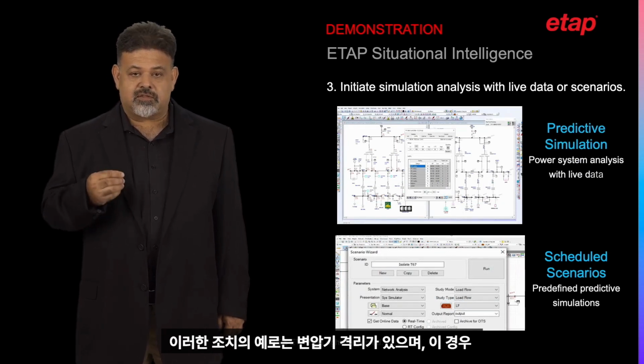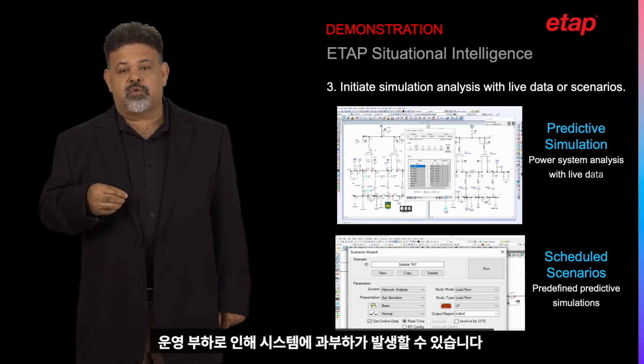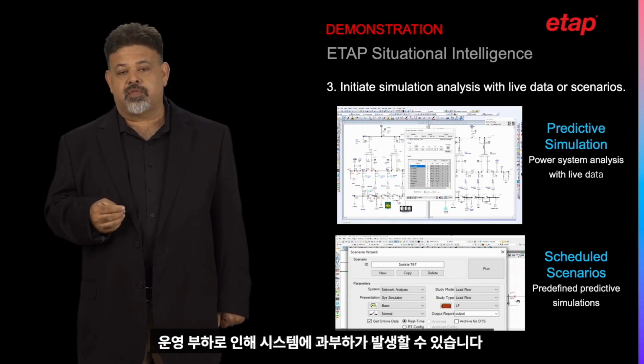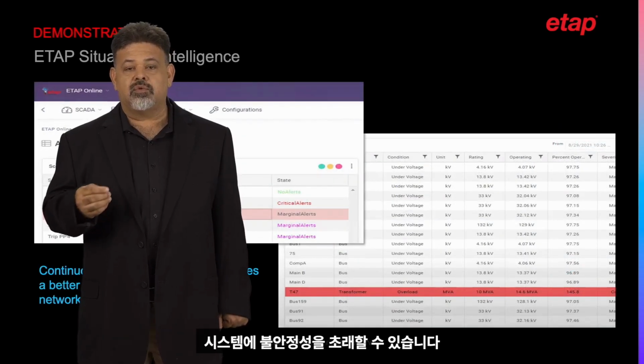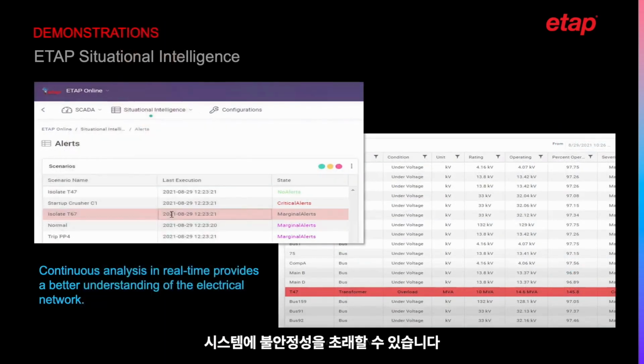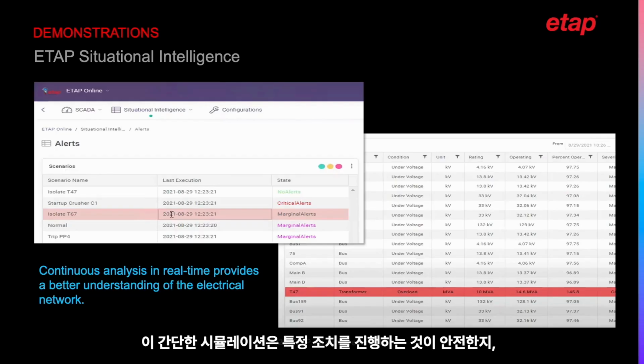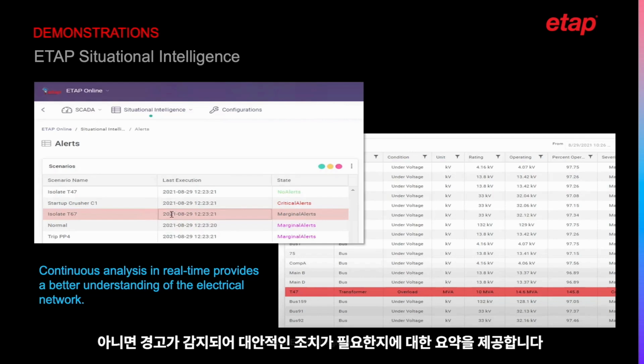Examples of such actions can include isolating a transformer, where the operating load may cause an overload in the system. Another example is the start of a large motor that can cause instability on the system due to the power required during the startup. These scenarios are then visualized by the operators and observed for any potential unsafe conditions for specific events. This simple simulation can provide a short summary to the operator on whether proceeding with an action may be safe or if alerts are detected, and it may require an alternative course of action. This continuous power analysis in real time provides a better and simpler understanding of the network.